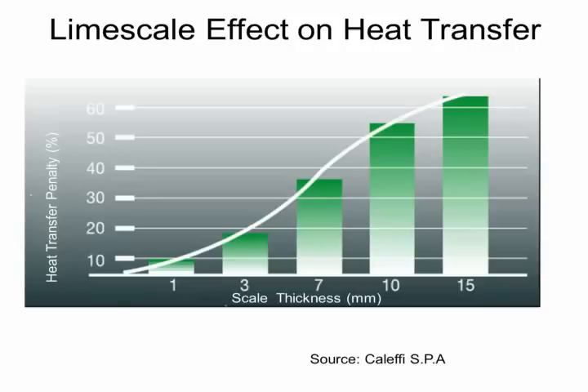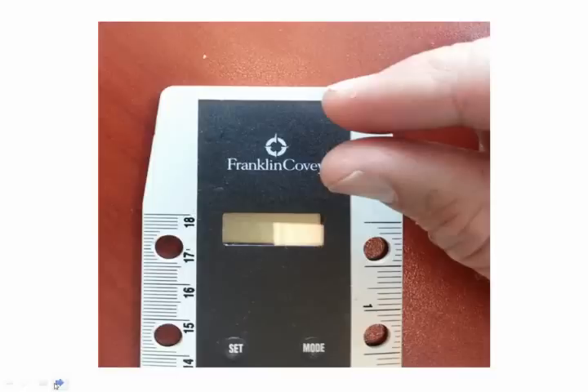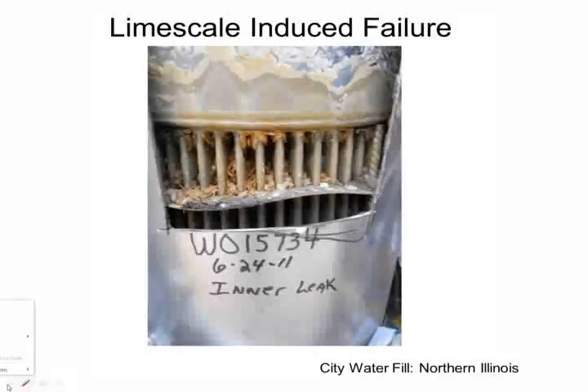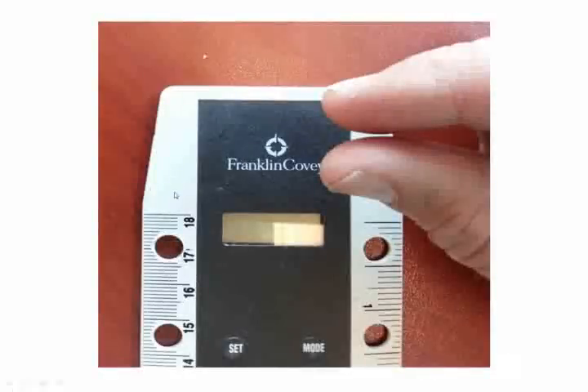It's the high temperature side of the system, typically your boiler in this case, a heating system, where you're going to scale up. And those boilers, those heat exchangers don't like scale. So, we'll show that here in just a second, but to give you an idea, for all of us south of the Canadian border who don't understand metric, what is 1 millimeter? Well, there's my finger, and the space between my fingers shows what 1 millimeter is. It's very small, and doesn't take much to get 1 millimeter.